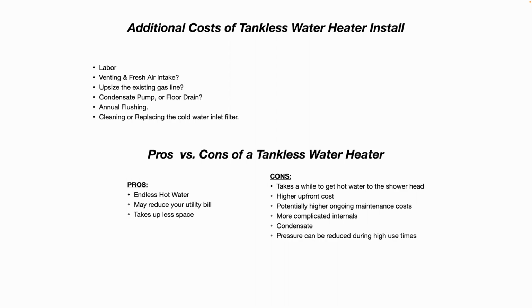And I say may reduce your utility bill because if you think about it, that tankless gas-fired water heater not only is consuming gas, but to run all the electronics on that tankless water heater, like that blower motor, fan, the PC board, the solenoid valves, that all consumes electricity. Whereas with a standard tank type gas-fired water heater, they do not consume any electricity. Now, if you have one of the high efficiency tank type water heaters where it's got the fan on top, then that's a different story. But again, we're talking about just a standard, normal tank type gas water heater compared to a gas-fired tankless water heater.